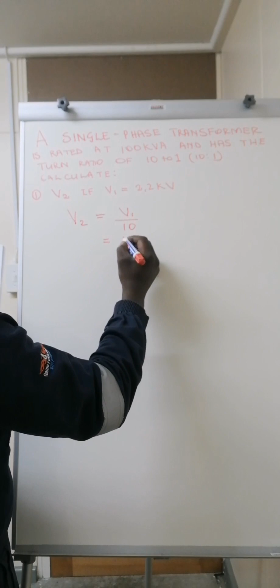So to calculate this, let's go for it. V2 is equal to V1 over 10, that's our 10 ratio. So V2 equals 2.2, let me simplify it, 2.2 multiplied by K, which stands for 1,000, giving you 2,200. Then you divide by our 10 ratio, which is 10, and it equals 220 volts. So that's our first value that we've got.